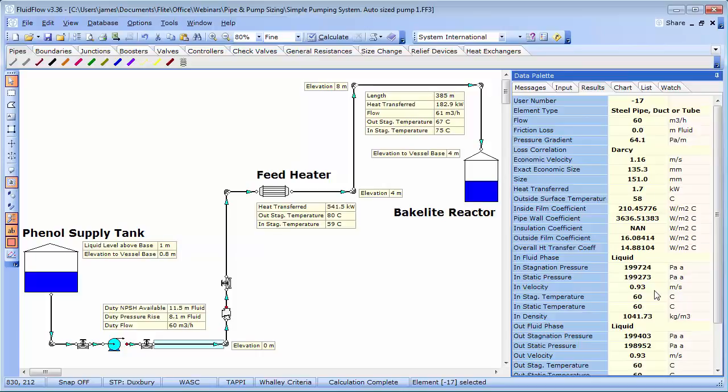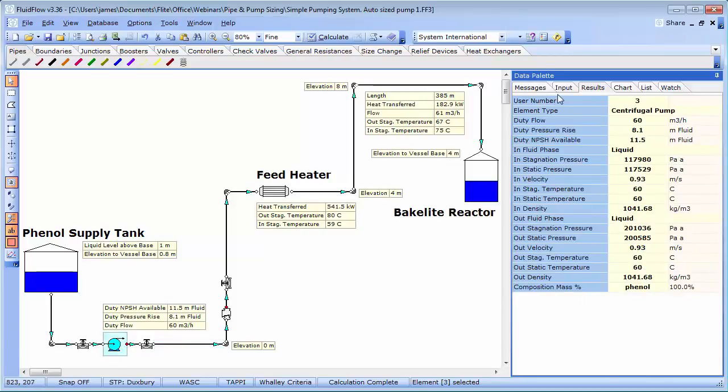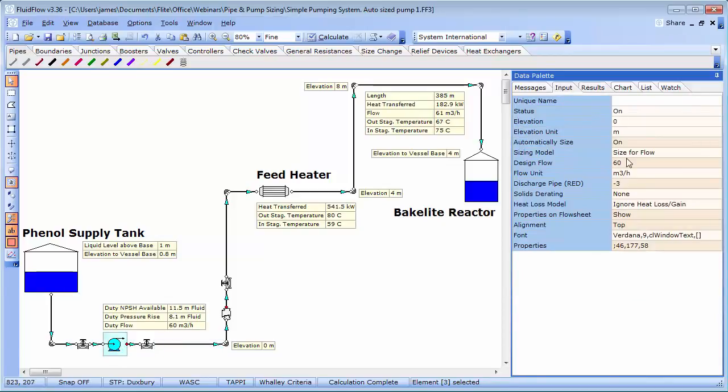This means we are now ready to complete the system loss calculation. Which determines the total head required by the pump. Sizing the pump means specifying the head and flow at which the pump will operate. This is called a duty point. And remember, a pump will always operate where the pump performance curve and system curve intersect.